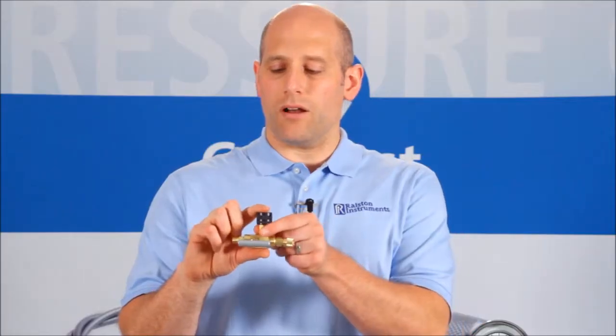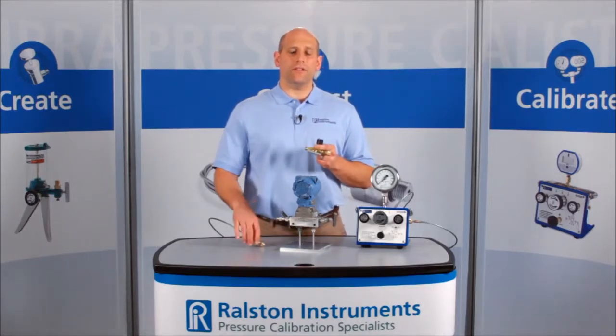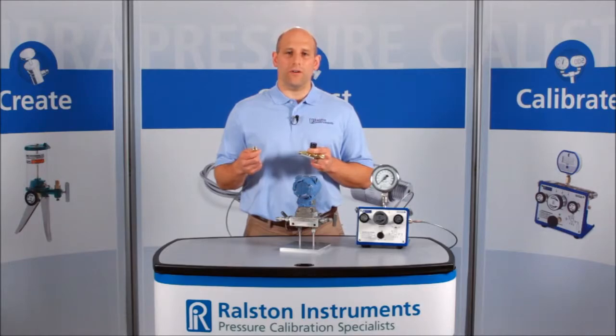This allows you to block off the pressurized side completely and vent pressure only from the process side. When you have to do multiple tests, this valve makes it easy to connect to another device without venting the entire hose.